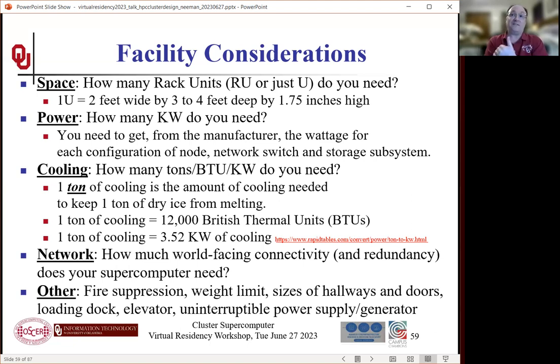There's the weight limit, typically measured per tile. You may have seen in your data center these 2 foot by 2 foot tiles with holes in them to let the cool air come through. Those are called pedestal floor tiles, a raised floor where the concrete floor is anywhere from 6 inches to several feet below. The pedestal floor tiles are held up by metal girders or whatever you want to call them, and there's typically a weight limit associated with those tiles.